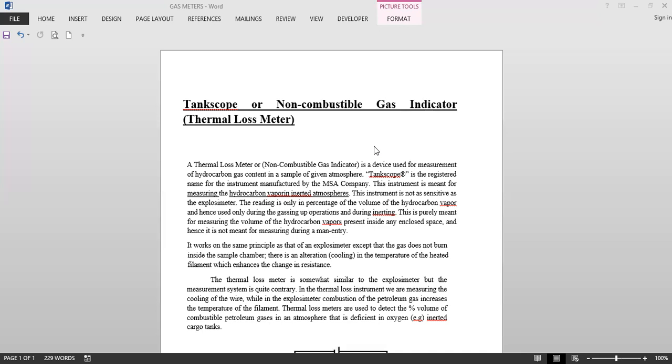The instrument is meant for measuring the hydrocarbon vapors in inerted atmospheres. That means you can use this tank scope when the oxygen inside the space is less than 8% also, or even less, or whatever is the amount of oxygen does not matter.